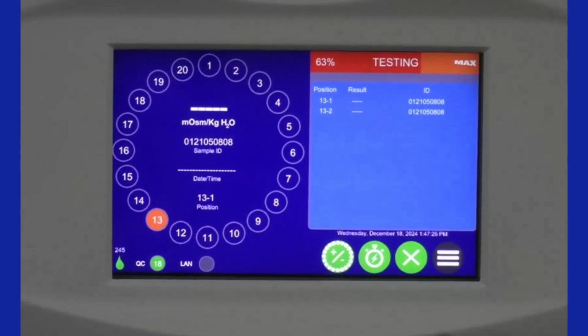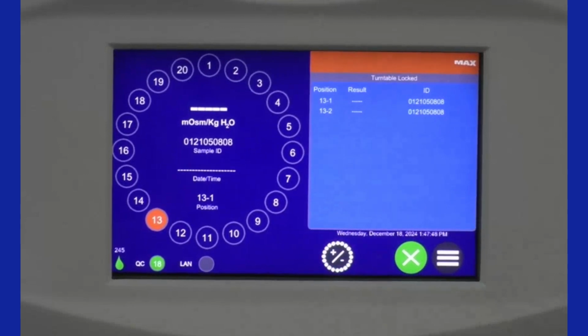So another cool feature is, let's say when you get that patient sample of that patient who potentially ingested that toxic alcohol, let's say you have samples on here that you just loaded up in positions 1 through 10, and you're only on test number 3. You have this really cool button here, which is a stopwatch with a little lightning bolt, so it actually looks pretty cool too. You can go ahead and click that. It'll make a little beeping noise, and up here it says select positions. So what I would do is pick a spot that I want to load my stat test. So if I'm in positions 1 through 10, maybe I'll throw it in position 11. And then I can scan in that tube, put it in position 11, and then hit start.